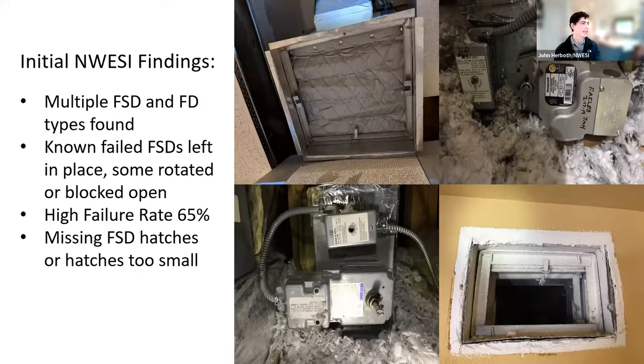Our initial findings here: we found multiple dampers, both fire dampers and fire smoke dampers, failed. We were at a 65% failure rate, which is, like Larry was saying, very high. And a lot of hatches were missing, or too small. Here in Oregon and Washington, you need at least 1 square foot. If you can't get that on a duct that's too small, then you need to make it a removable duct. We've even asked about adding 2 hatches so you can get 2 hands in there on smaller ducts, and the fire marshal said no thank you and stuck to code. That bottom right picture is obviously coated with texture, and you replace that fusible link.